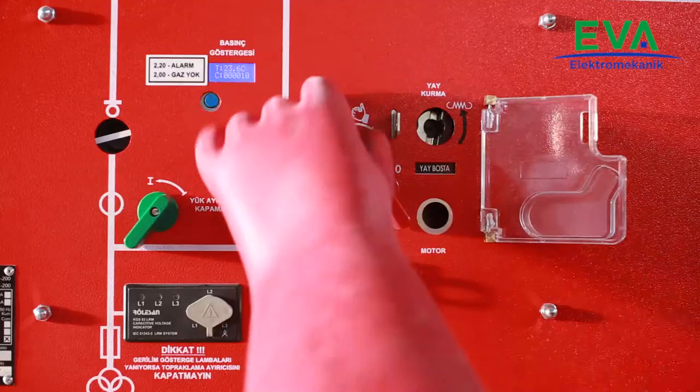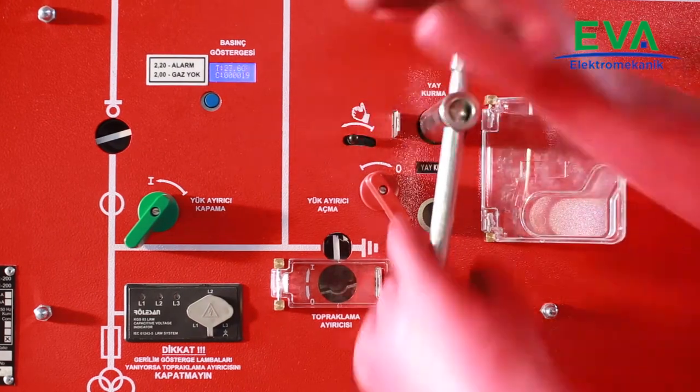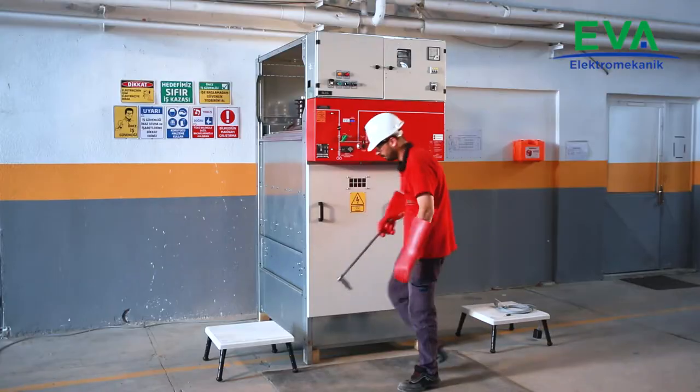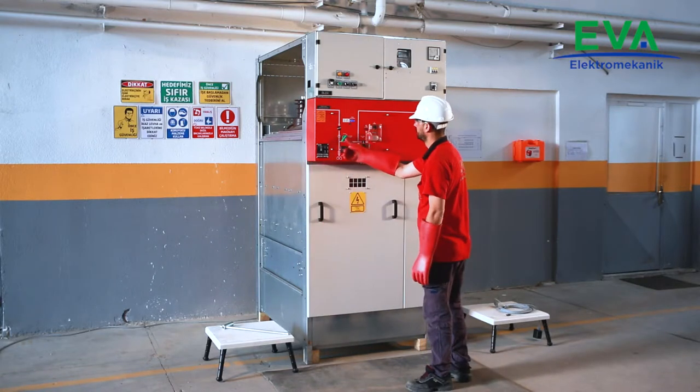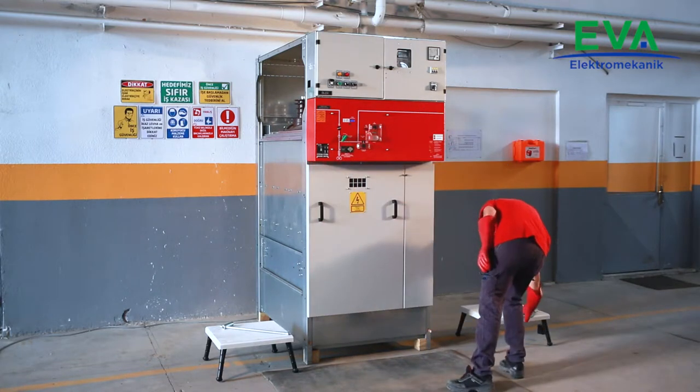Charge the closing spring of the load break switch. If the cubicle is motorized, the spring will be automatically charged when the motor button is turned clockwise. Close the load break switch either from the mechanical button over the mechanism or from the remote control cable with electrical buttons.